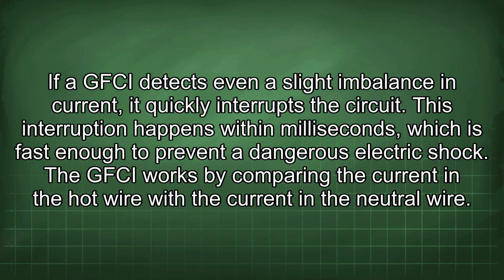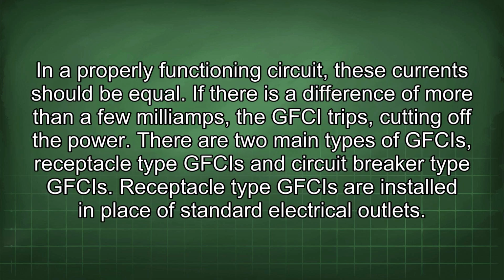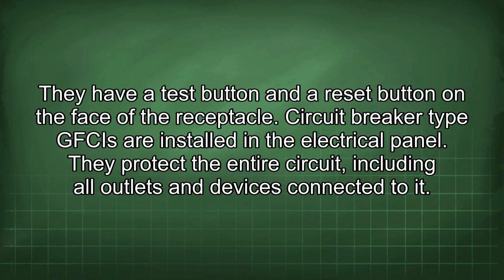The GFCI works by comparing the current in the hot wire with the current in the neutral wire. In a properly functioning circuit, these currents should be equal. If there is a difference of more than a few milliamps, the GFCI trips, cutting off the power. There are two main types of GFCIs: receptacle type GFCIs and circuit breaker type GFCIs. Receptacle type GFCIs are installed in place of standard electrical outlets. They have a test button and a reset button on the face of the receptacle. Circuit breaker type GFCIs are installed in the electrical panel. They protect the entire circuit, including all outlets and devices connected to it.